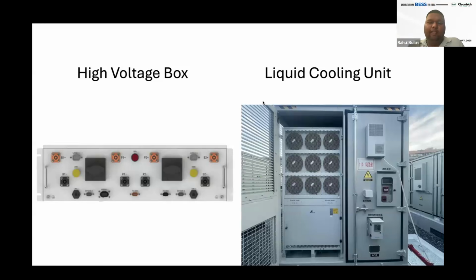And this is a liquid cooling unit. Today, as we all know, the 5 MWh container is the most popularly used system. In there, this kind of liquid cooling goes, and these are typically rated at 60 kW. 60 kW does not mean the power rating, it is the cooling capacity - so typically the power rating would be 60% of that, 35-36 kW kind of thing. That is at full capacity at 55 degrees, although 55 degrees doesn't happen every day. And for the battery to have 55 inside, outside should probably be 60 plus, which is unheard of, at least today.